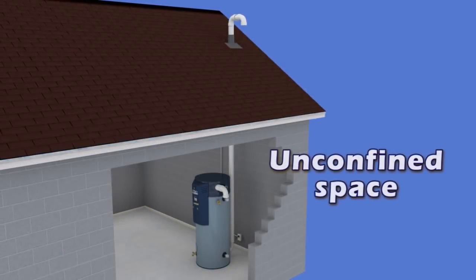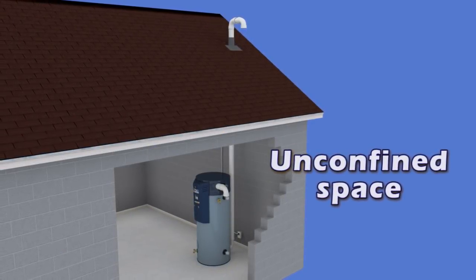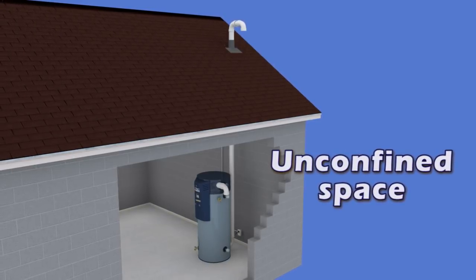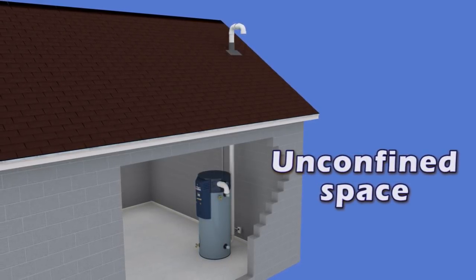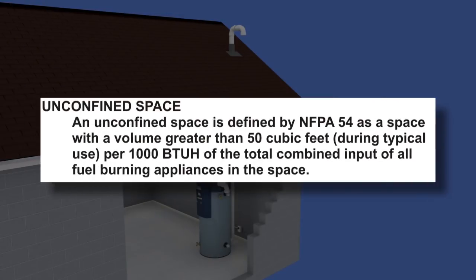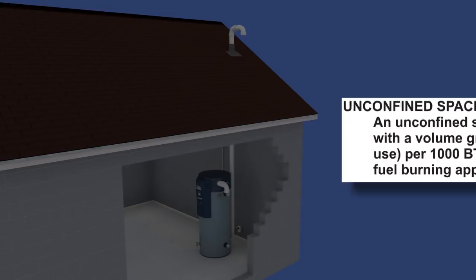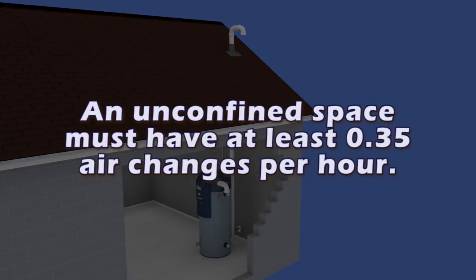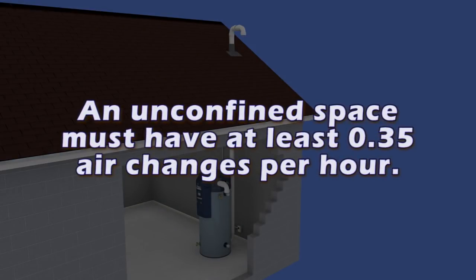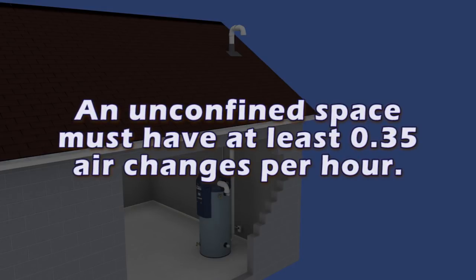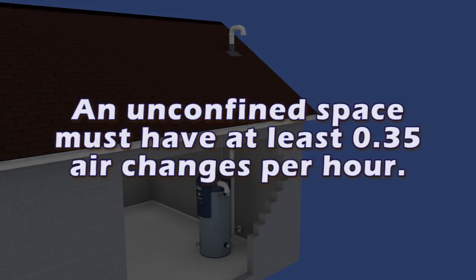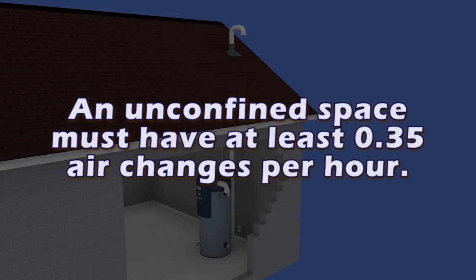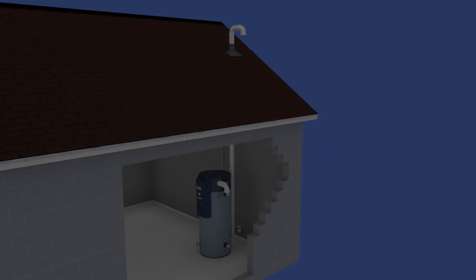A power vent system draws combustion air from inside the building. To do this, the requirements for unconfined space must be met. An unconfined space must have a volume greater than 50 cubic feet per 1,000 BTUs per hour of total combined input of all fuel-burning appliances. Also, any space that has 0.35 air changes or more per hour can be considered unconfined. But with vapor barriers and other tightening of buildings, this condition is becoming less likely.